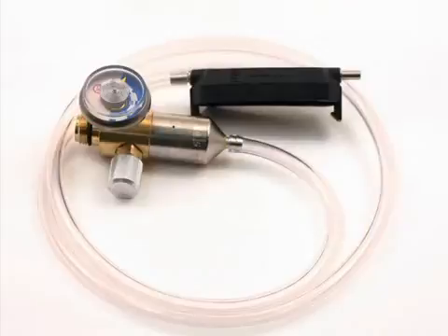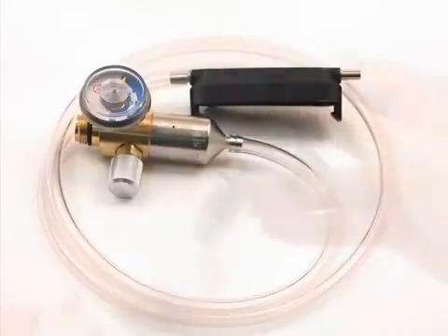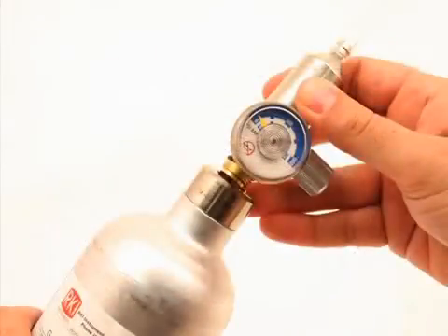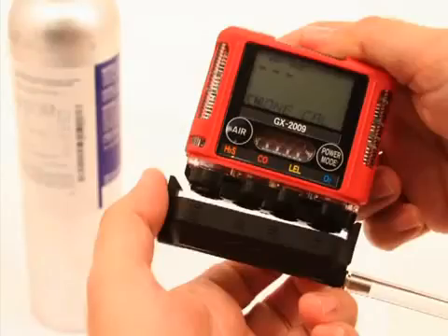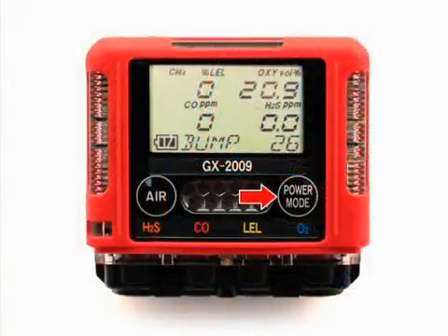Use the sample tubing to connect the calibration adapter plate to the regulator. Attach the tubing to the adapter plate on the inlet side. Confirm that the regulator on-off knob is turned all the way clockwise, closed, and screw the calibration gas cylinder onto the regulator. Push the adapter plate onto the GX 2009's sensor face. Make sure the adapter plate is oriented with the sensor names on the adapter plate matching up with the sensor names on the instrument. Press and release the power mode button.